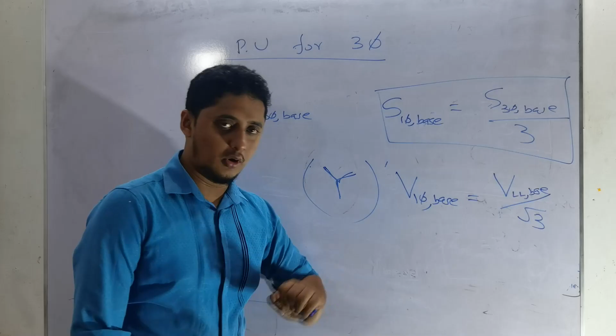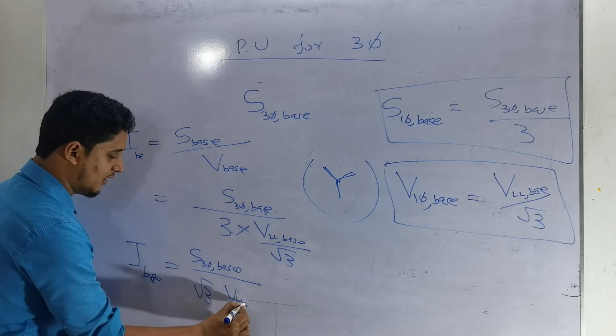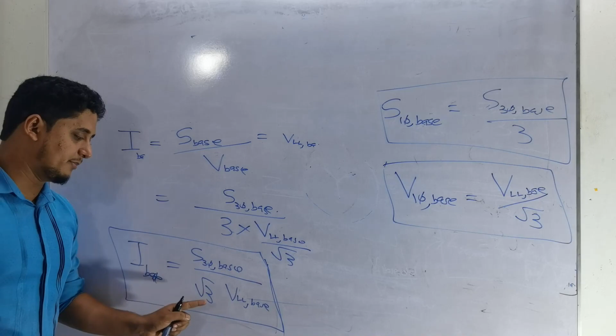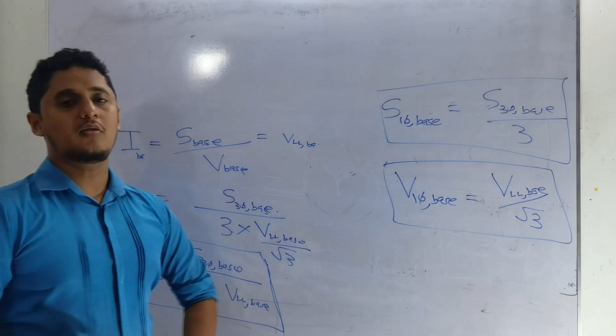We know current is equal to base current equals base power divided by base voltage. Single-phase base power is equal to 3-phase base power divided by 3, and single-phase base voltage, if you consider the Y connection, equals line-to-line base voltage divided by root of 3. From that, base current equals 3-phase base power divided by root of 3 times line-to-line base voltage.